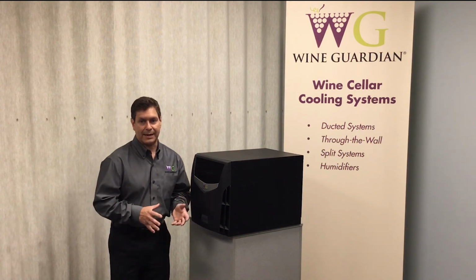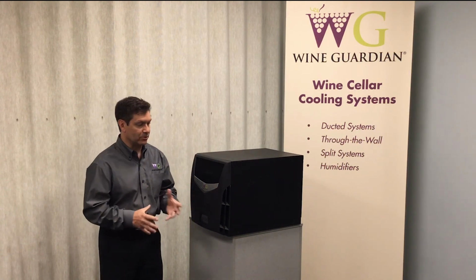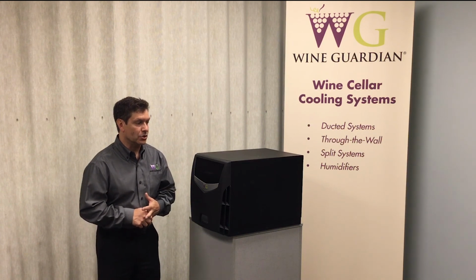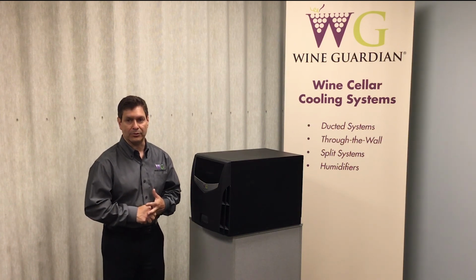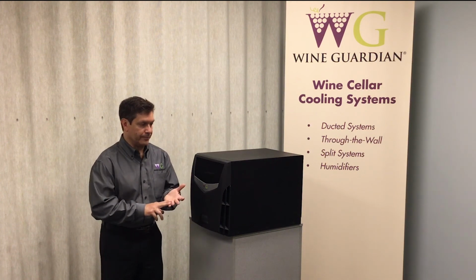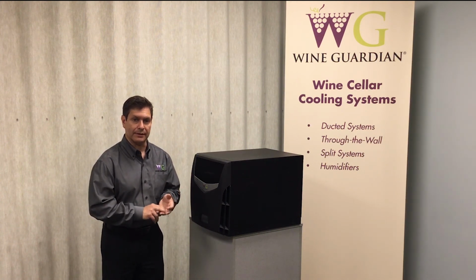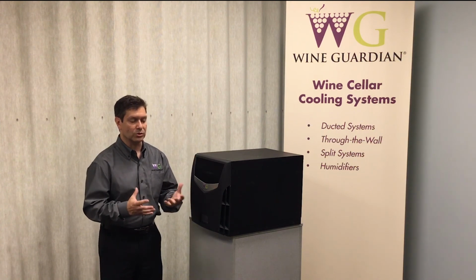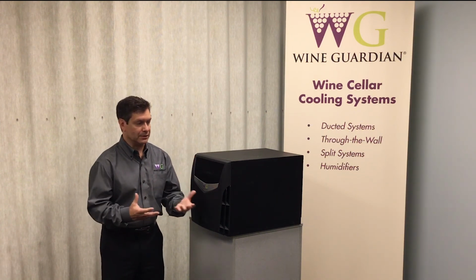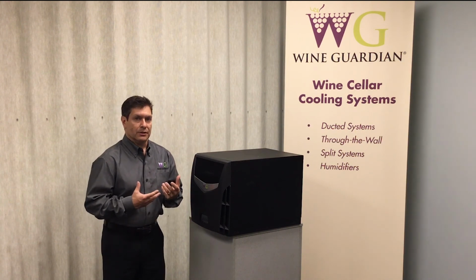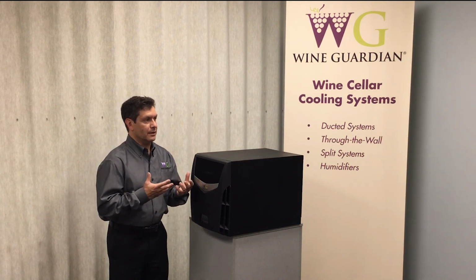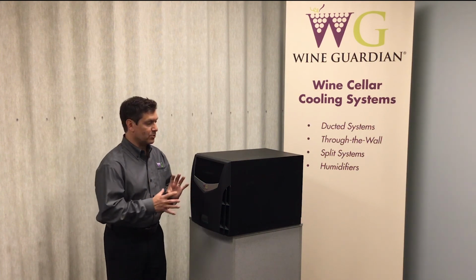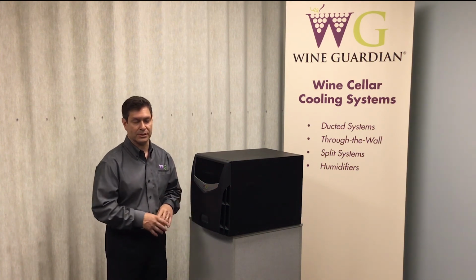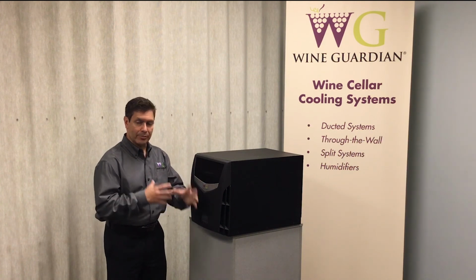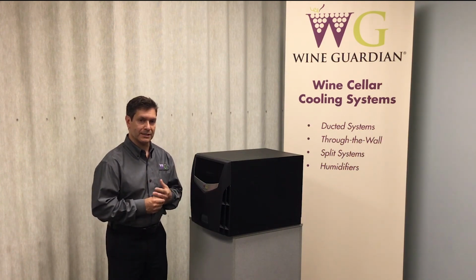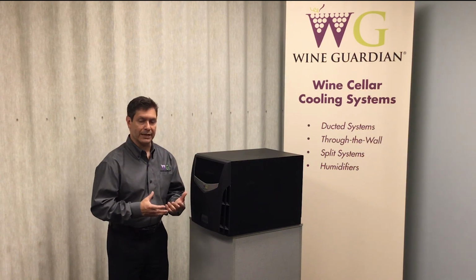Can it be mounted near the floor? Generally, we don't like to see that application. Floor placement or low on a wall is not a proper area to mount a through the wall unit. One, typically hot air rises, so you tend to generally have a colder room at the lower parts of your structure. You like to mount the unit 5 to 6 feet off the floor, someplace where you can view the controls and access the controls. This gives you a better mix of warm and cold air throughout the space, and is a better operating system.